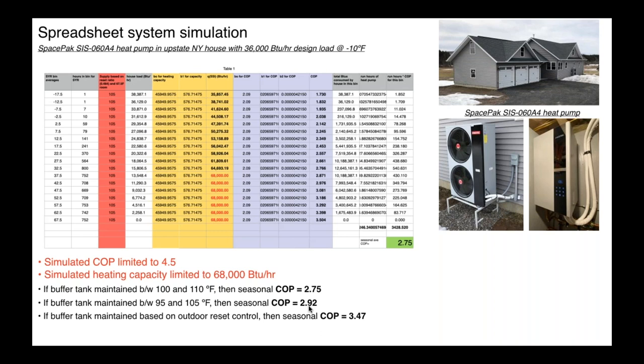I want to show you what happens, though, if we go to a full outdoor reset on this scenario. If I calculate what this temperature is based on outdoor reset, we jump up to about 3.4 on our seasonal average COP. And again, that's a really good performance number. It compares favorably with what a geothermal system does. Yes, geothermal heat pumps can provide higher COPs under certain conditions than air source. You really can't just take a snapshot of either heat pump and say, all right, here's a snapshot of performance of the air source heat pump. Here's a snapshot on the geo.